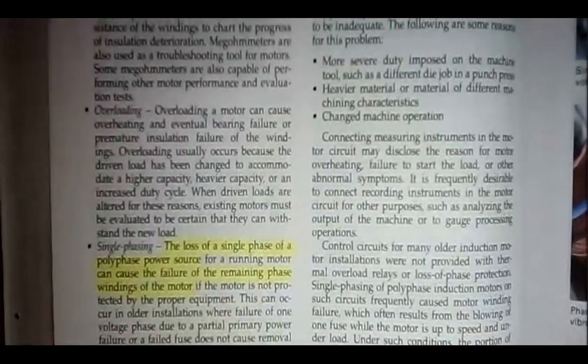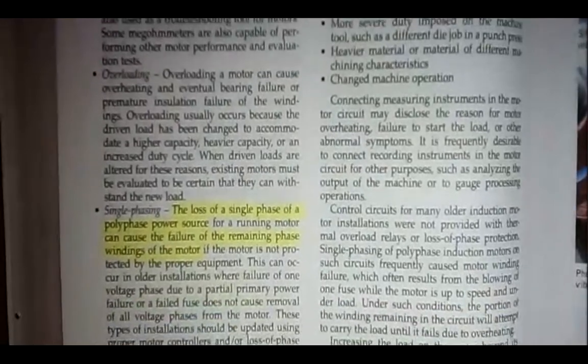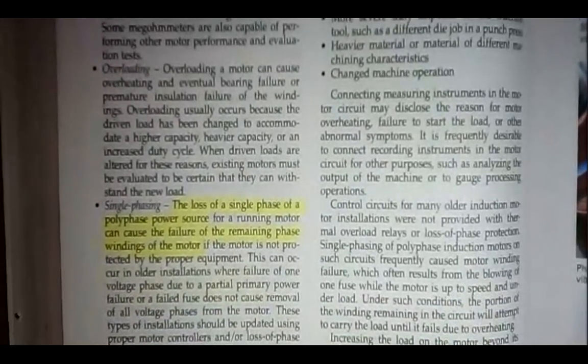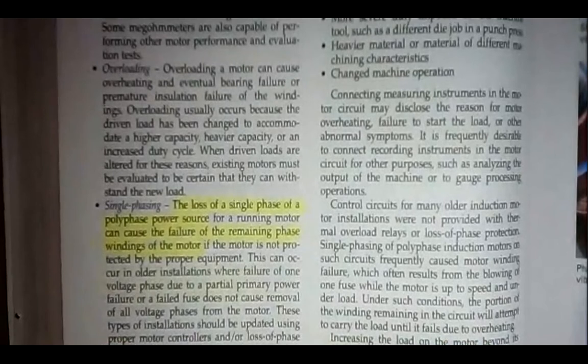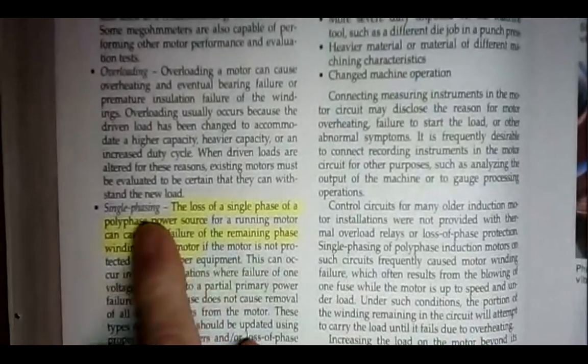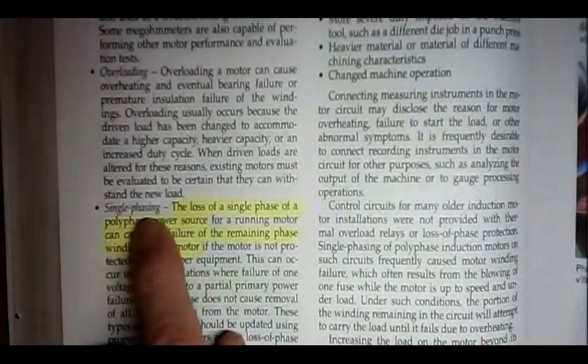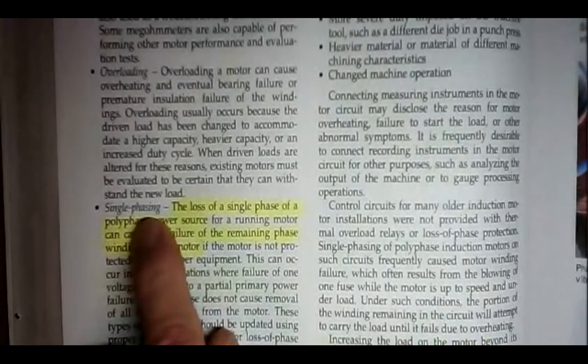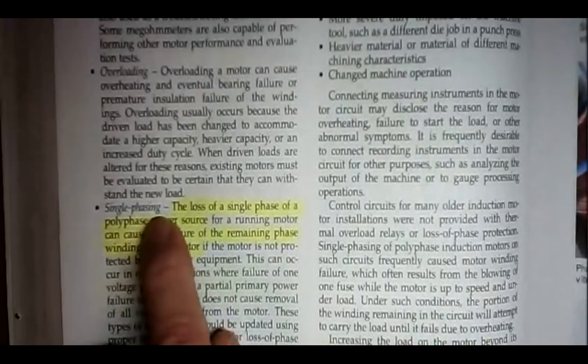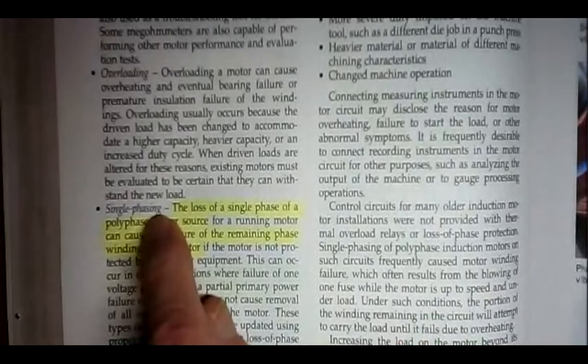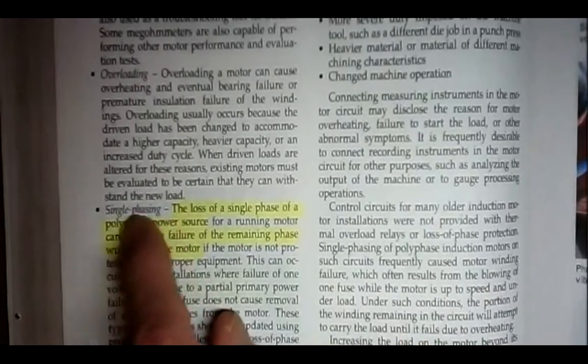On page two, on the left-hand side, they're talking about polyphase or three-phase motors. Three-phase motors. You can start a three-phase motor with three phases. It'll run with two. You can lose a phase while it's running. You cannot start a three-phase motor with only two phases, but it'll run.